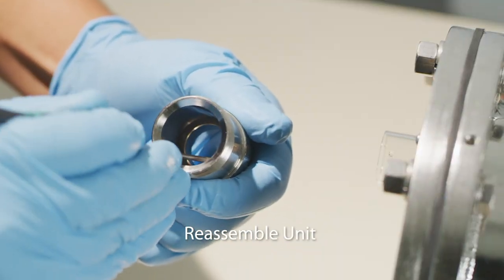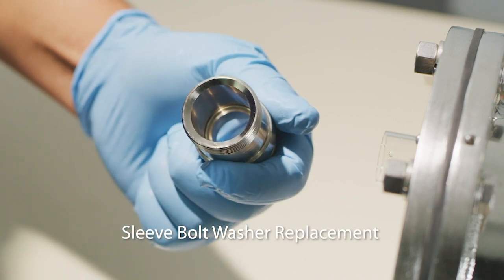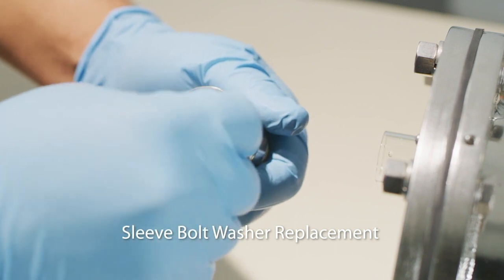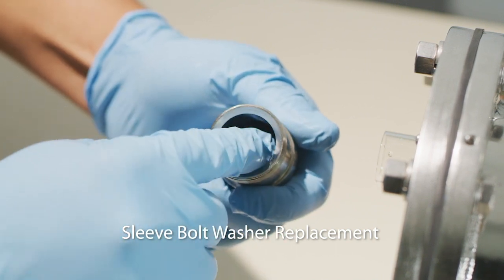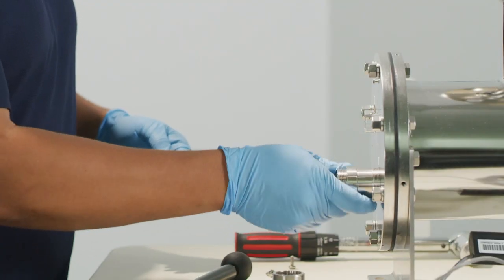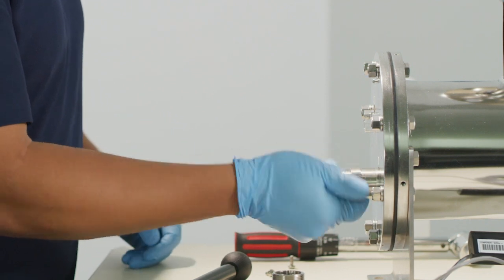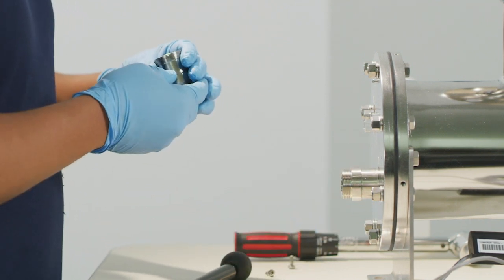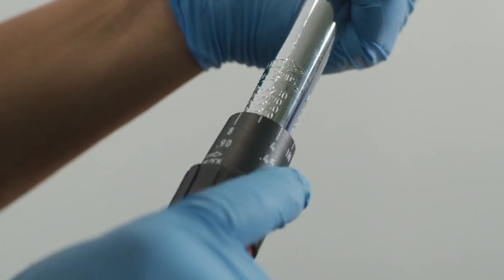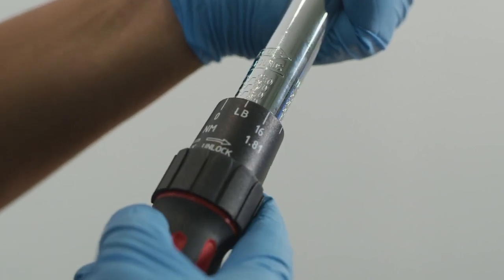Reassembly of the unit can now begin. Start by replacing the sleeve bolt washer by prying out the old washer and carefully seating a new washer with your fingers. Hand-tighten each sleeve bolt into place. As the sleeve bolt is tightened, it will properly seat the sleeve O-ring as well as push the sleeve into place. Set an on-site 3/8 inch ratchet to 100 pounds per inch and, using the provided compression nut tool, tighten each sleeve bolt.